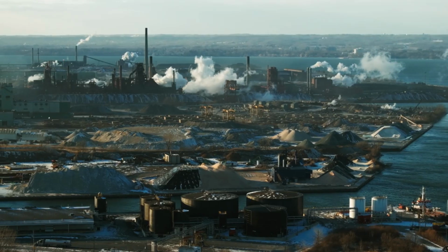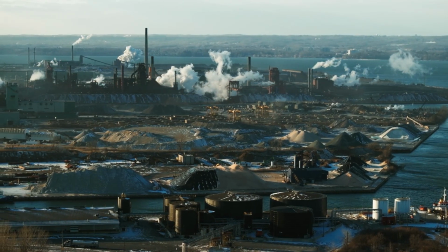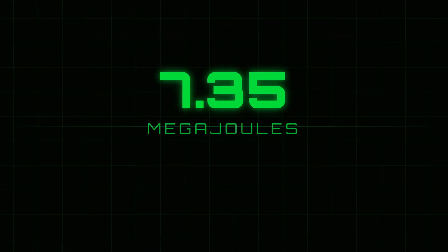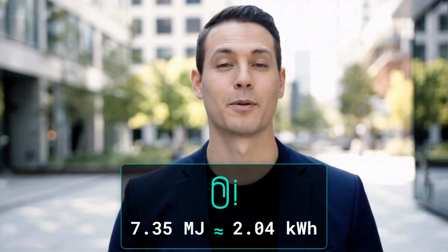Here's a practical example. You're heating a 250 kilogram steel tank from 20 to 80 degrees Celsius. Input mass, 250 kilograms. Specific heat capacity, 490 joules per kilogram Kelvin. Temperature change, 60 degrees. The calculator instantly shows you need 7.35 megajoules of energy. That's roughly 2 kilowatt hours, helping you size your heating system appropriately.